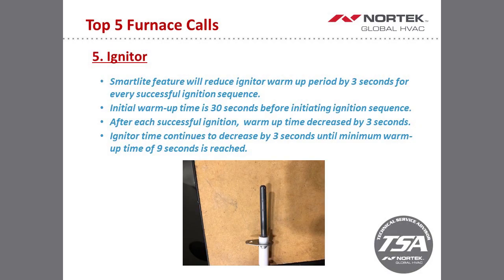Now, as a side note, for the guys that may be out in California with the new G8 furnace, the Smartlite feature is not on that furnace, and that's mainly due to the variable speed inducer motor that we had to put on that furnace in order to get the G8 furnace built. But the G7 furnace will have the Smartlite feature, and it's on the previous models of the G7 as well. So I just wanted to make sure you guys are aware of the Smartlite feature in case you're finding the igniter only staying on 9 seconds or 12 seconds, for example.